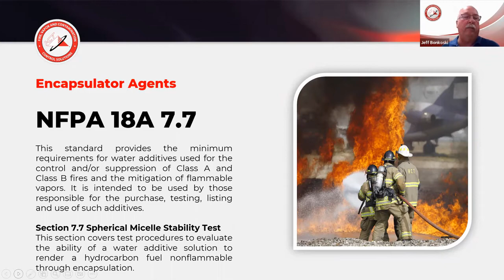At the end of that initial flame test, the solution sits for 2 hours. At the end of 2 hours, the flame is again passed across the entire surface of the pan, and again there can be no visible flames. The test can go on and on until that evaporates away, with no visible flames throughout that evaporation process.